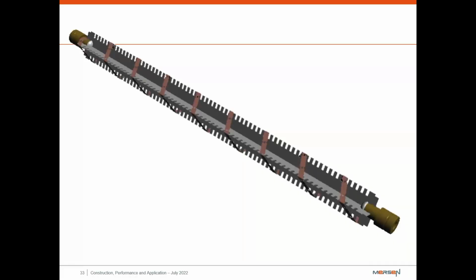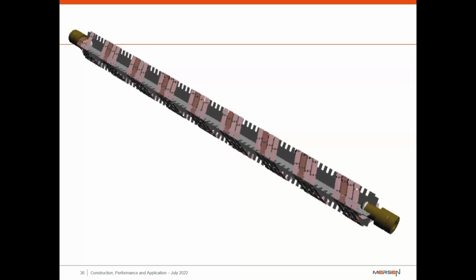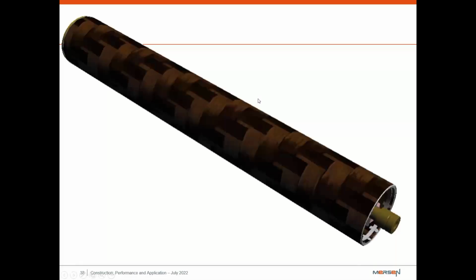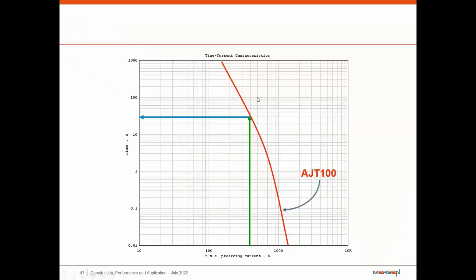So say that this element is going to be a 100 amp element and you want a 400 amp fuse. We're just going to have 4 of these in parallel as they wrap around. So the same principle applies. These are going to be the short circuit elements in here. So in the case of a fault, these will be wrapped in that sandy material. But we're going to have our end on one side and then our body that goes around it, and then our encapsulated.